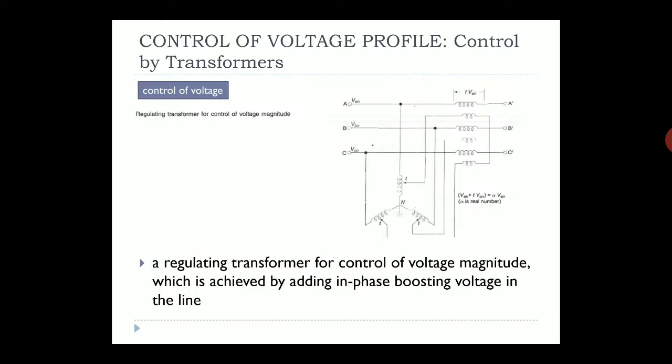A regulating transformer for control of voltage magnitude uses an on-load tap changer connected to a three-phase line to control the voltage output. This is achieved by adding an in-phase boosting voltage in the line. The boosting voltage is added using an additional transformer, and the voltage is obtained from the tap changer on the control transformer.